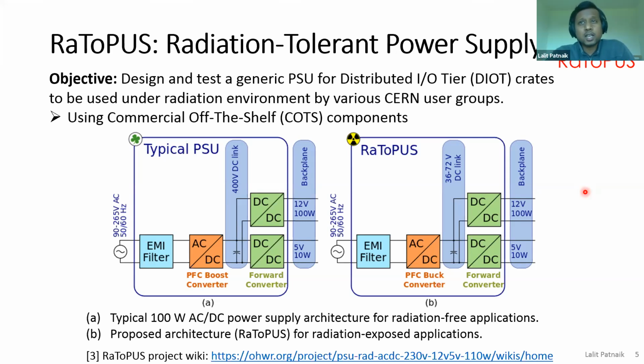Actually, I would say no. From a dynamic loading perspective, most of the dynamic loading is handled by the local capacitors in the load, but also by the DC-DC stage. The DC-DC stages are designed to have much larger control bandwidth, so they handle most of the dynamic loading, and hardly any is handled by the PFC stage. So in that sense, it's not a very stringent requirement.